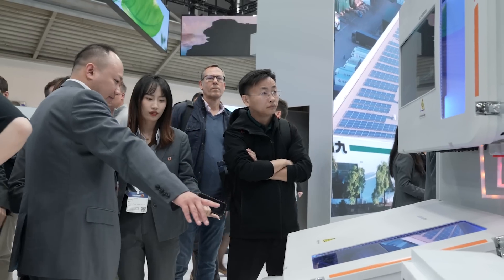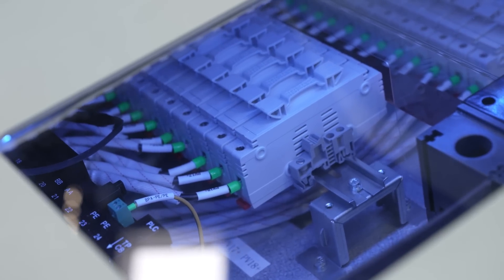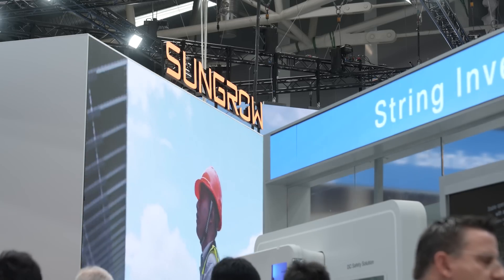Has intensive testing been conducted and how do you ensure the quality? We designed a special test for temperature in a climate chamber with more than 300 measurement points. We also have a large lab to simulate wind conditions in every direction, to be sure that not only the inverter but also the medium voltage station works as per parameters.